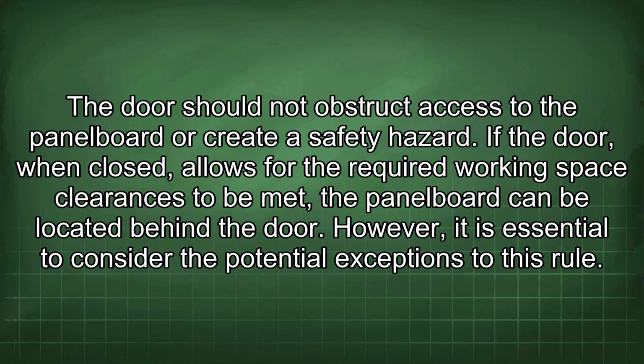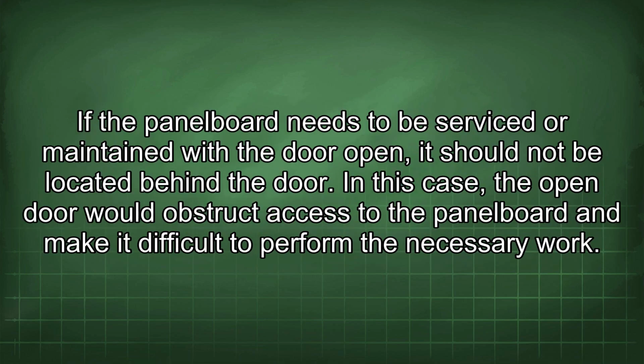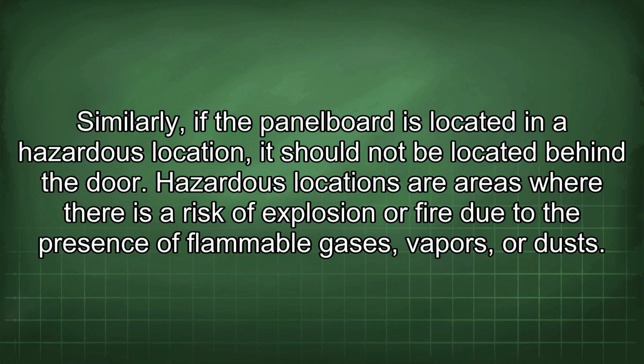If the door, when closed, allows for the required working space clearances to be met, the panel board can be located behind the door. However, it is essential to consider the potential exceptions to this rule. If the panel board needs to be serviced or maintained with the door open, it should not be located behind the door. In this case, the open door would obstruct access to the panel board and make it difficult to perform the necessary work.